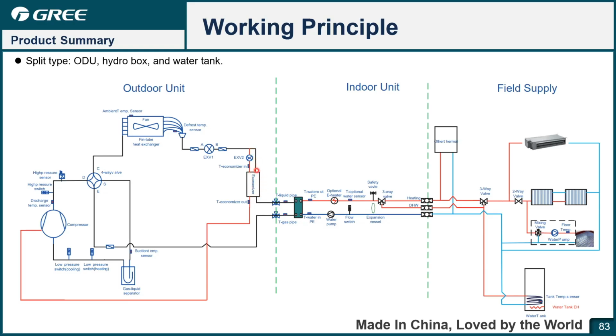If the ambient is very low, is very cold in the winter, and then in this case, this expansion valve 2 will open to throttle and distribute some refrigerant exchanged heat with the major pipe so that some gas can flow back and inject to the compressor to cool down the discharge temperature.